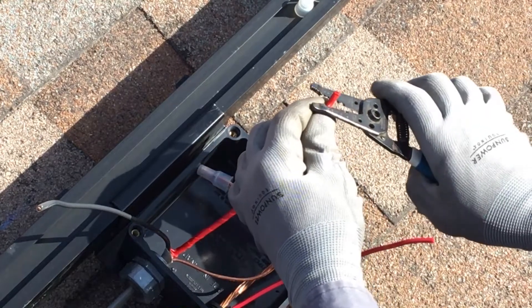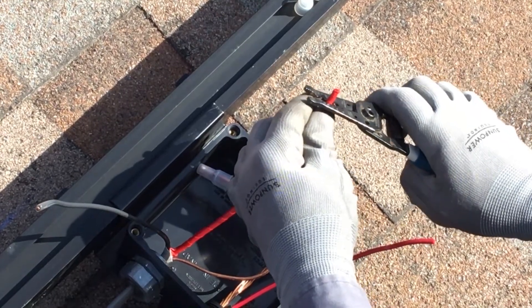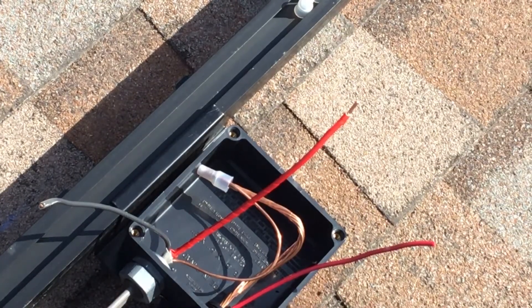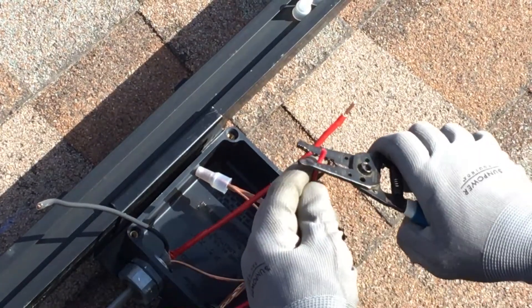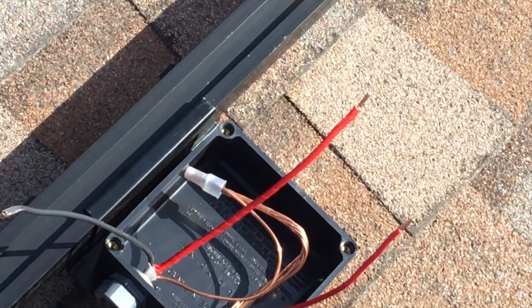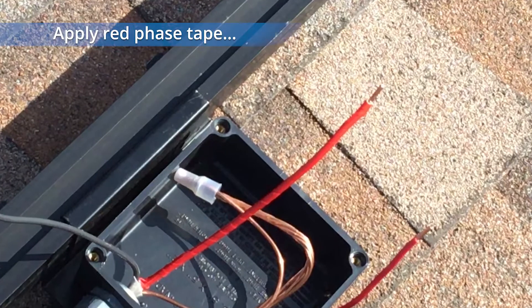First, strip the individual conductors, exposing about a half inch of the copper wire. The white wire in a UF or non-metallic cable assembly can be used as an ungrounded conductor, as shown here. If so, it is necessary to identify it using red phase tape or paint wherever it is exposed. For more information regarding NEC code compliance, please refer to the applicable guidelines.